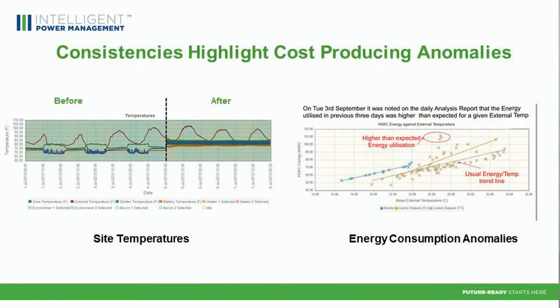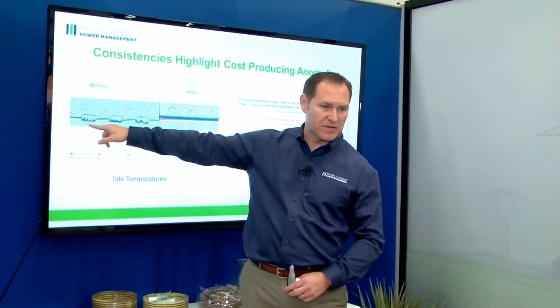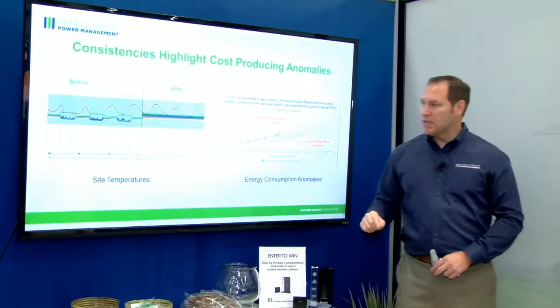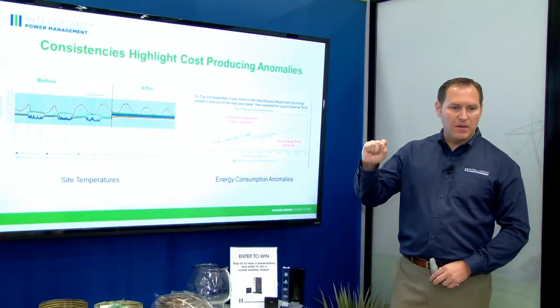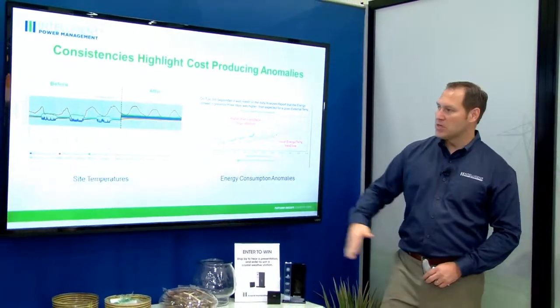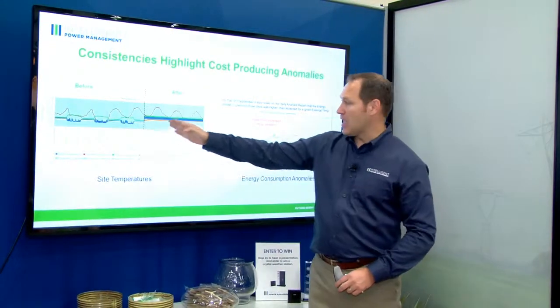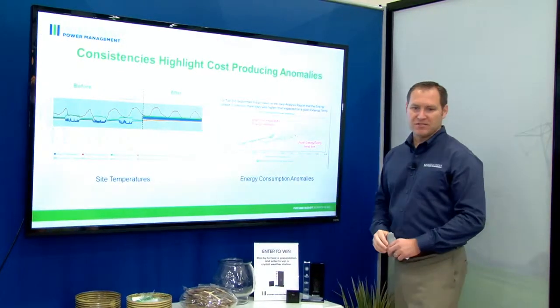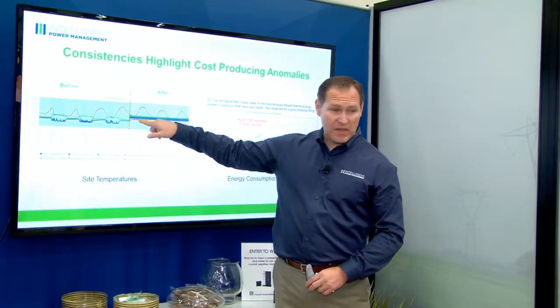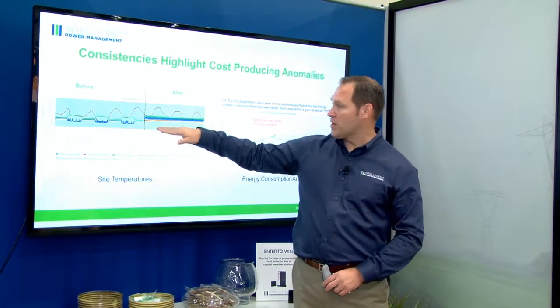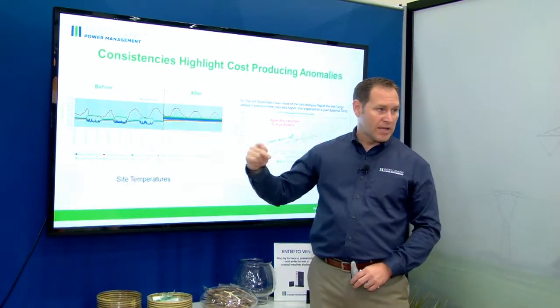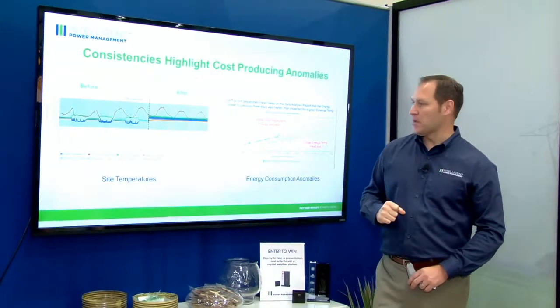But if you look at the daytime, it's different — the temperature of the blue is not quite the same. What we hyper-focused on is driving efficiencies in how the site operates so we can look for cost-producing anomalies. After the IPM solution, it's very consistent. The only thing that adjusts is outdoor temperature, whereas the indoor temperature stays very consistent. This allows us to rapidly pick out anomalies in the way the site operates.